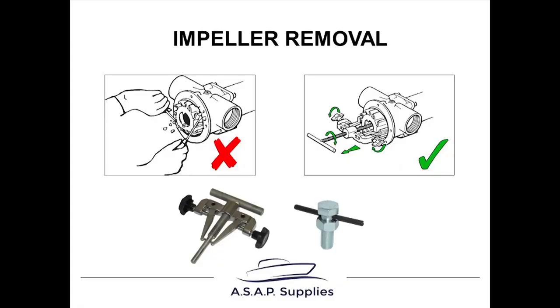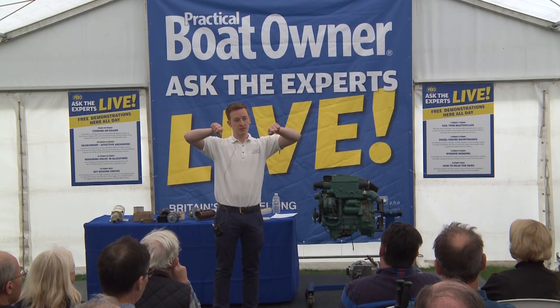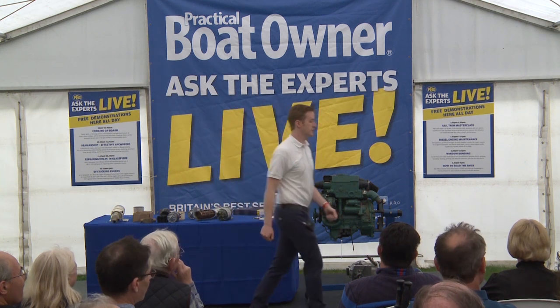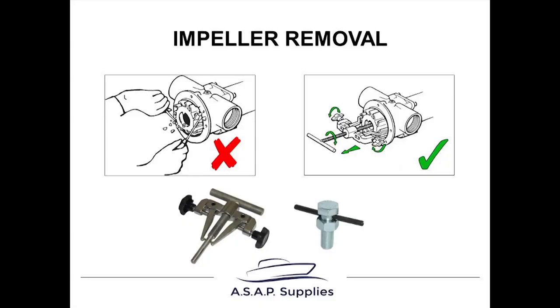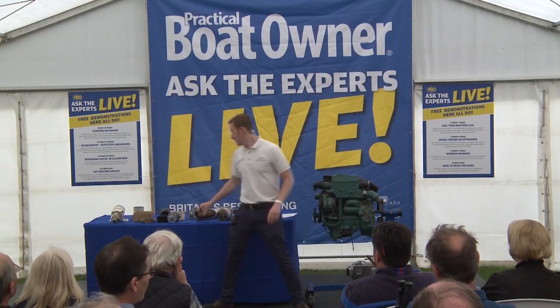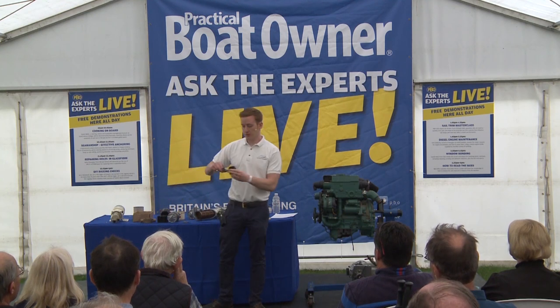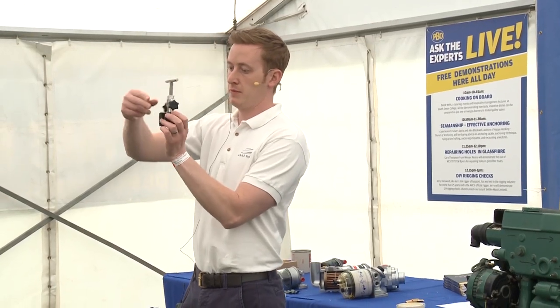Impeller removal. You tend to see, based on how the impeller wears the brass parts of the pump, people using screwdrivers to try to force it out, and what you find is marks around the top of the pump that scratch the brass. That impeller is spinning at say 1,000 to 2,000 RPM, so if there are any marks in there, it's just going to churn up the rubber. You really want it as nice and smooth as possible. So you get little impeller removal tools - little pincers that bite into the side of it.